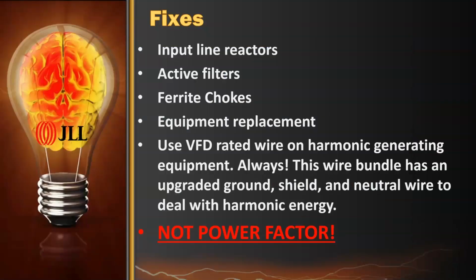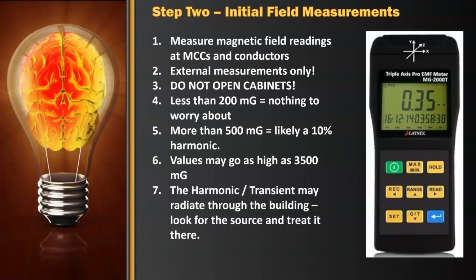And so step one, calculate the load factor. If it seems really high, then we might have a harmonic problem, and then we can do the next step, which was to get a Gauss meter and measure at the motor control panel. Measure how many milligauss it is, and if it's high, then maybe we have an issue. Now you said, but the next step is where I got lost. You said, okay, let's say it's really high, maybe 1,000 milligauss, and then you said, then you trace it back. What do you mean by that?